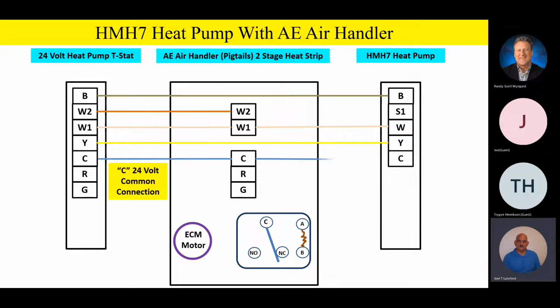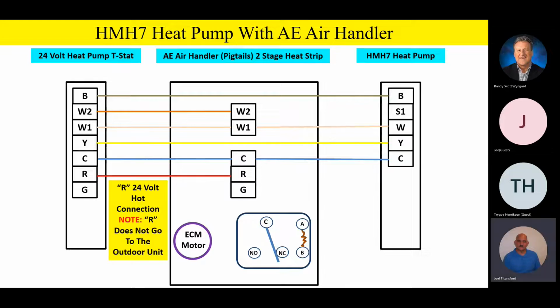C terminal goes all the way through. That's 24-volt common, and that would pretty well be expected. C from the thermostat to the common wire, that's typically a blue wire, goes outside to the C terminal outside. R terminal is our 24-volt hot.